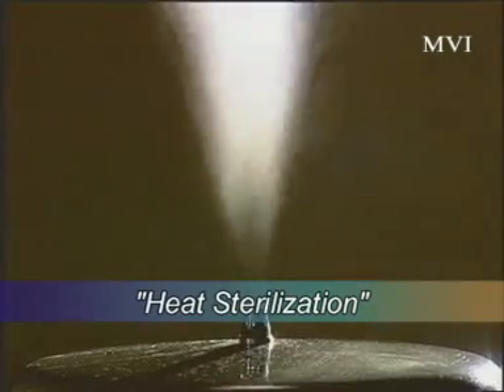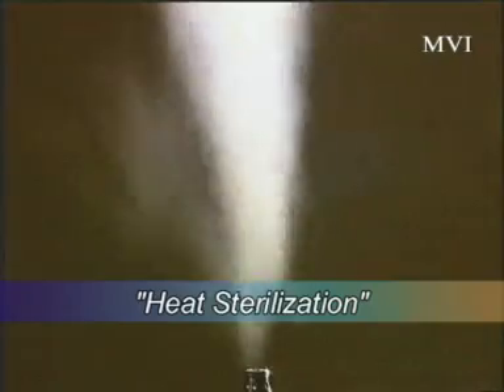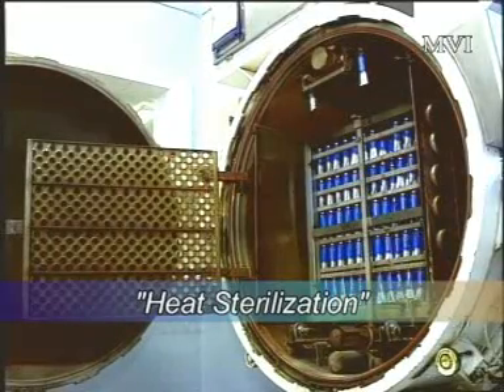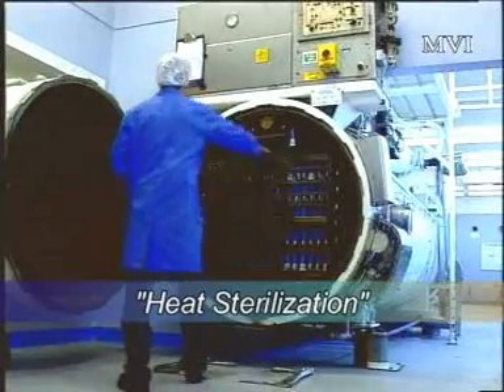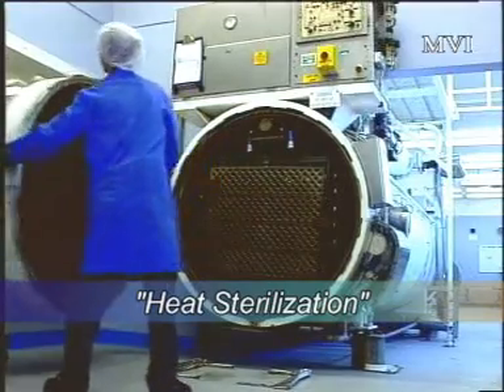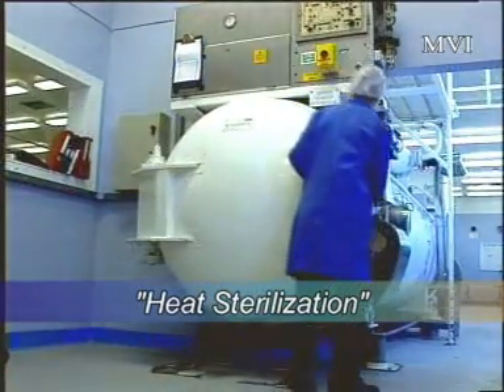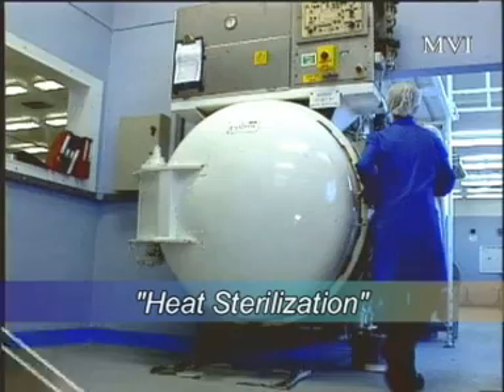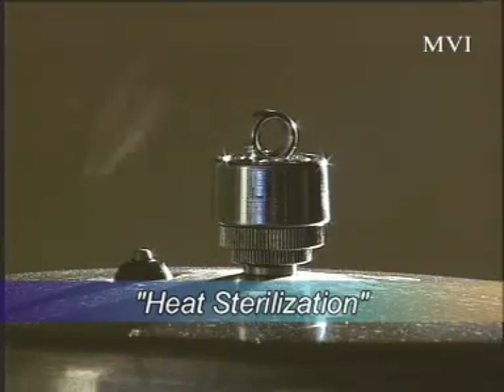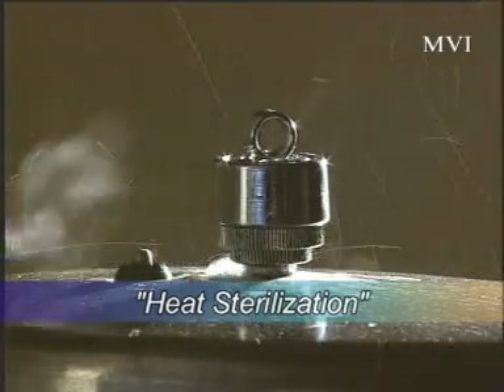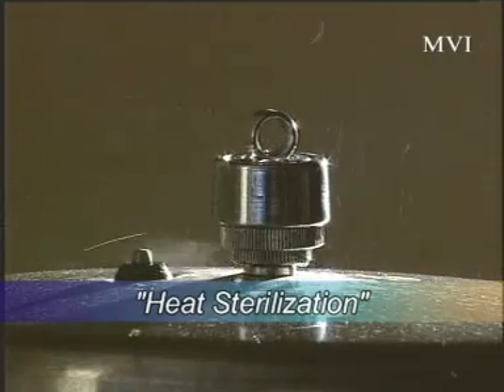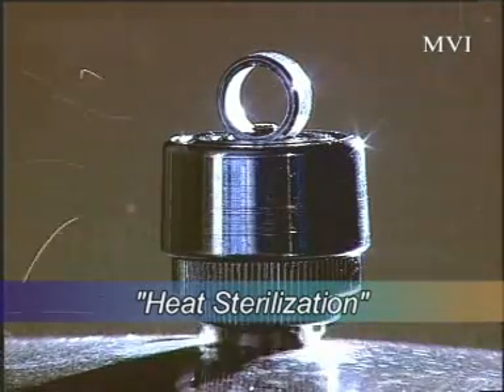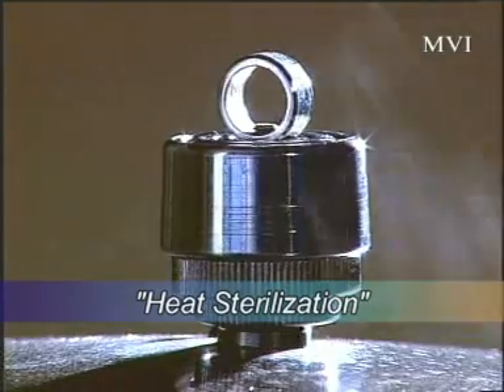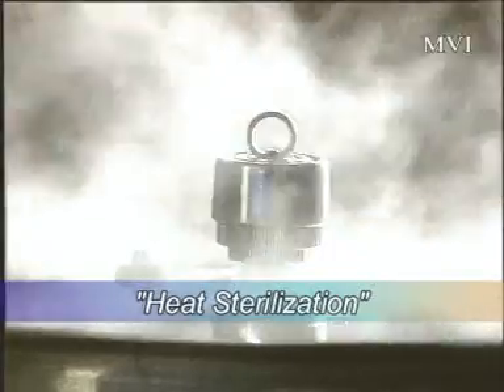With moist heat sterilization, the heating medium is steam supplied under pressure, rather like a domestic pressure cooker. This type of equipment is usually referred to as an autoclave. It's the combination of heat and moisture which together are lethal to microorganisms. To be achieved, a higher than atmospheric pressure is required. Of course, the pressure has no sterilizing effect. It merely permits higher temperatures to be reached, which is why pressure cookers work quicker than open saucepans.